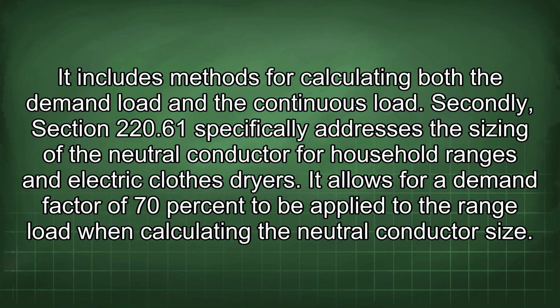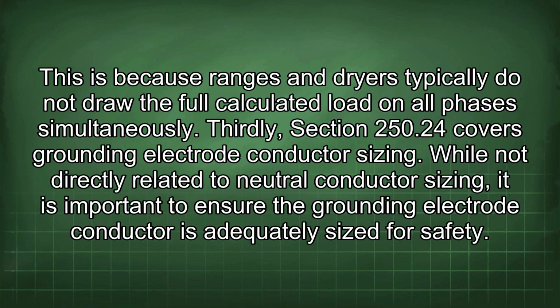Secondly, Section 220.61 specifically addresses the sizing of the neutral conductor for household ranges and electric clothes dryers. It allows for a demand factor of 70% to be applied to the range load when calculating the neutral conductor size. This is because ranges and dryers typically do not draw the full calculated load on all phases simultaneously.